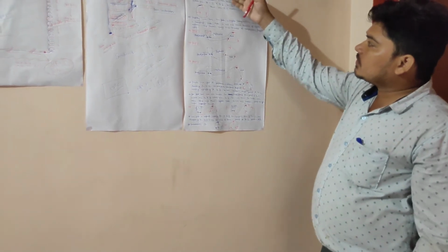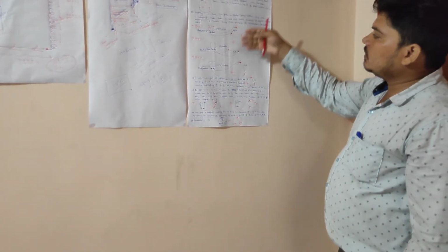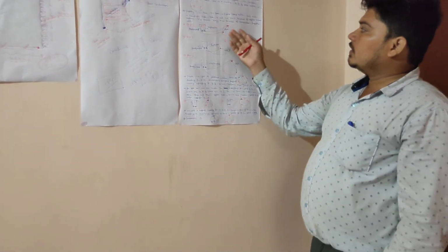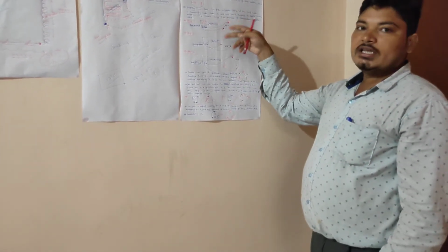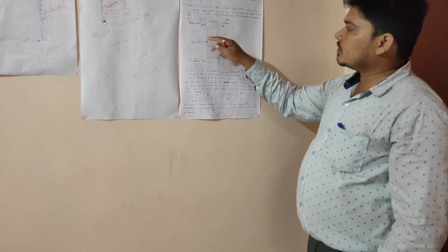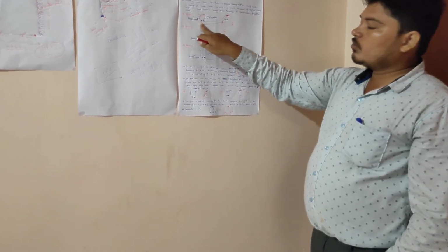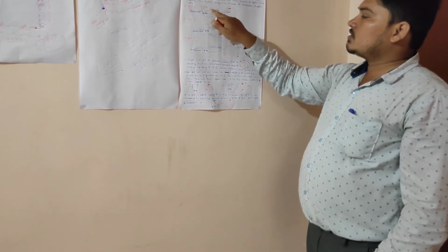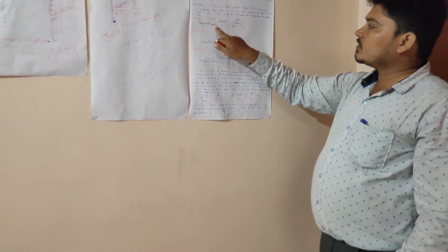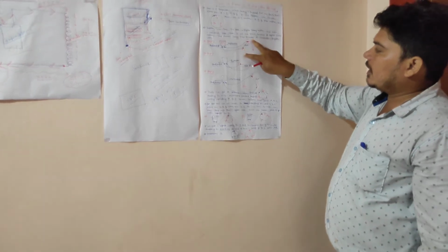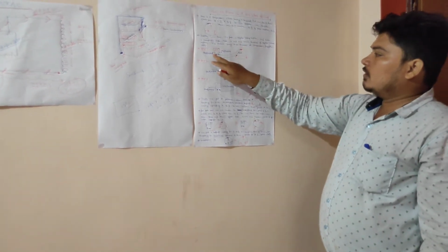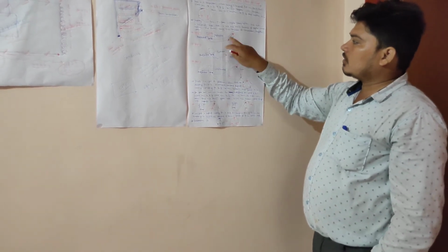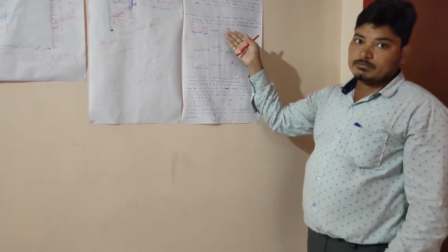So we can see here in 3 steps how to take a reading between every two electrical terminals of a compressor. In step 1, I repeat again, in step 1, this is a digital clamp meter. Take a reading between A and B with the help of the digital clamp meter wires, one black and the other red. We get 30 ohm.